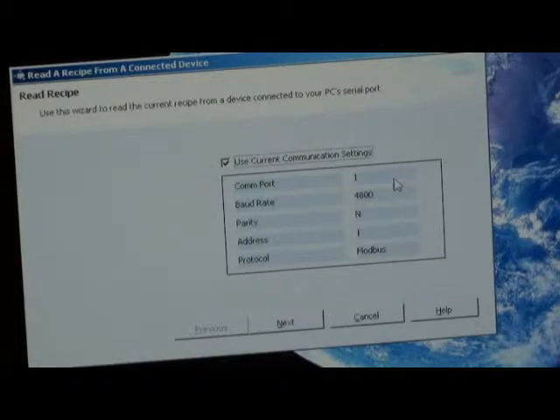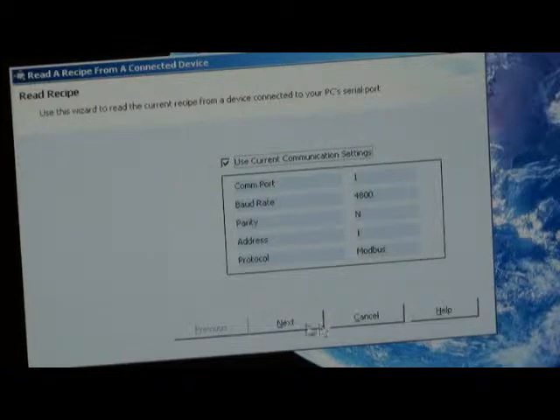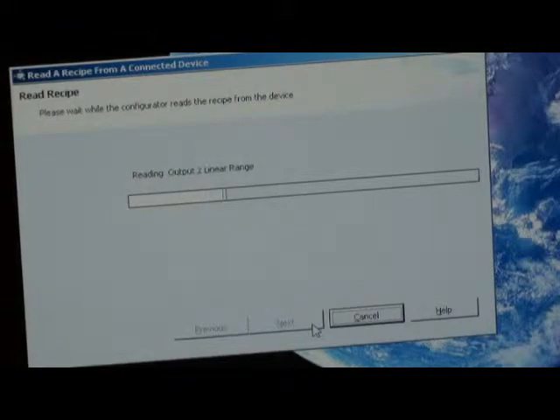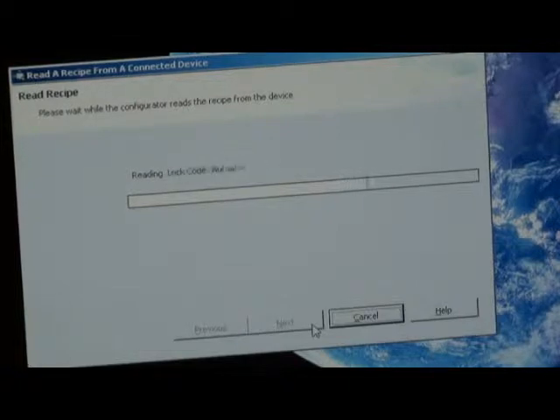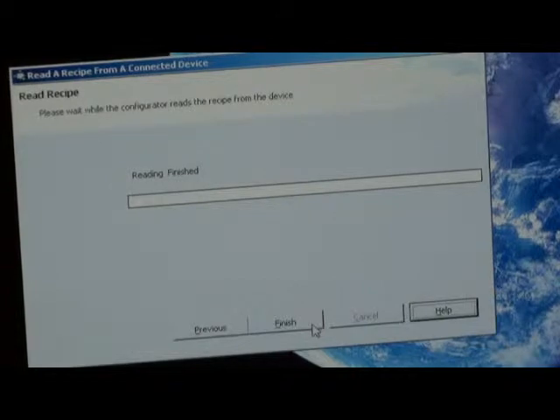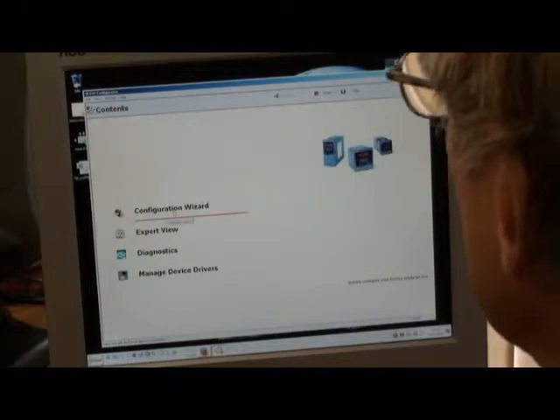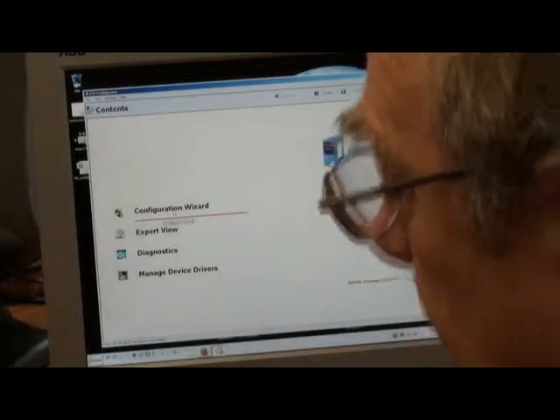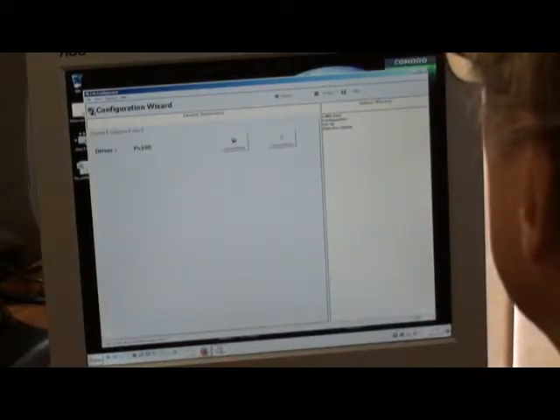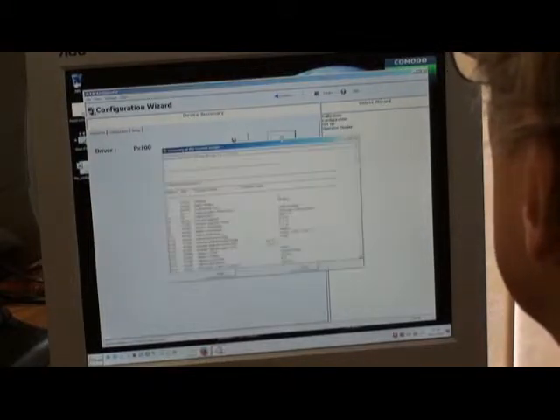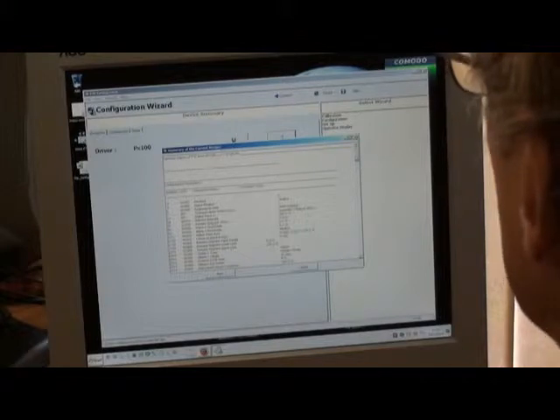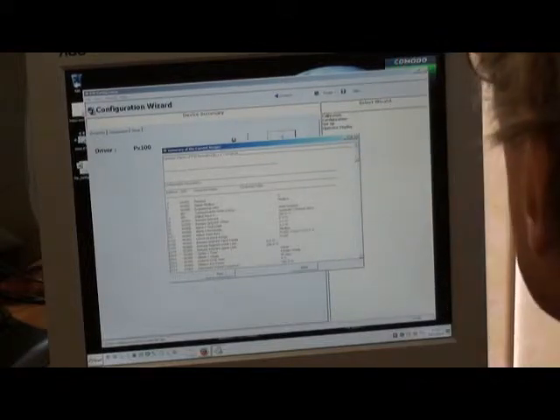Comm port 1, 4800, parity N for no, address 1, protocol is Modbus protocol. Okay, so this is where it will communicate with the device. It's finished reading, so it would have taken out all of the information that's in that controller. So let's go to the configuration menu. We can see a summary of the information that's in that controller. Let me expand it.